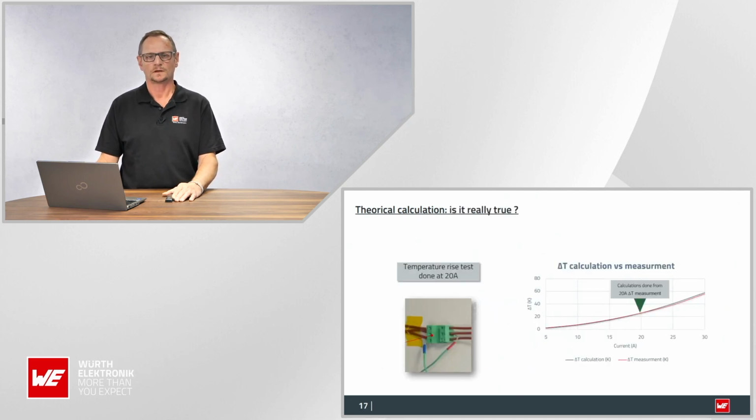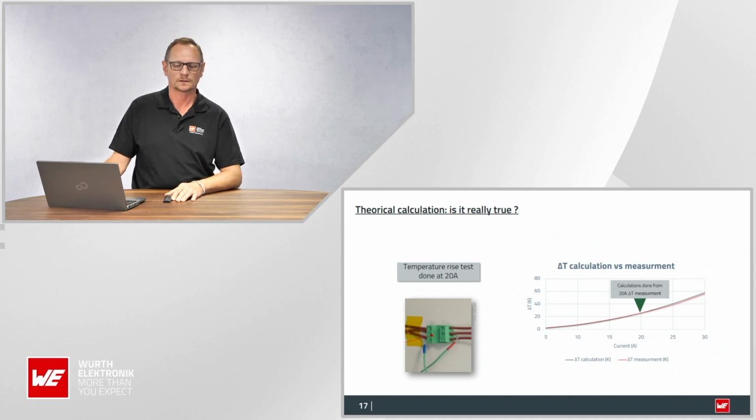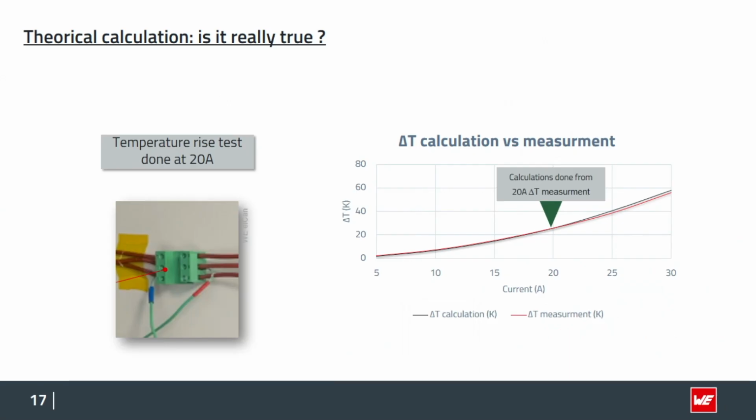And now we wanted to verify if this information is really true, and we tried to confirm this with the same connector. We did the temperature rise test at 20 amps, and we found this kind of line that you can see in the table on the right hand side.